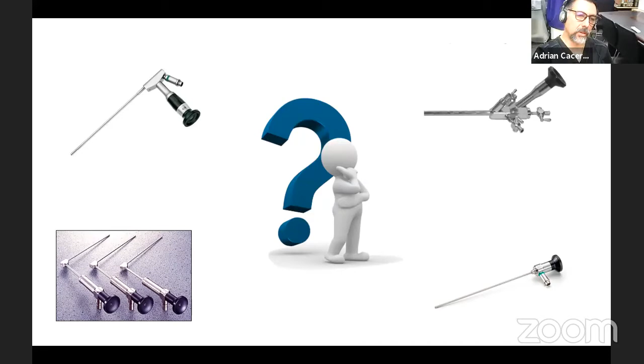And then there's the second system, which is now the most common one, in which specially designed glass rods are placed, and there's some air in between them, so the image is amplified. This is the so-called Hopkins, and these can come on a zero angle or various angles. We'll see that. And there's a fiber optic in which a bundle of fibers will produce an image, and it will be carried back, and then basically your camera will put all these tiny dots together and generate an image.